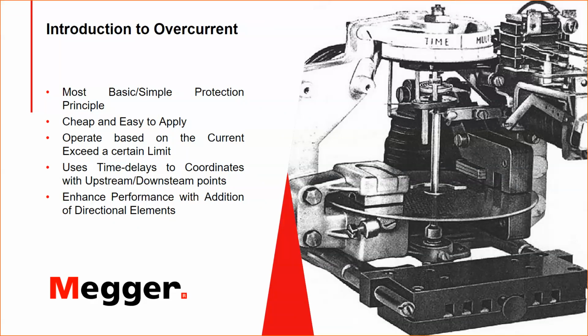Now, overcurrent can also be enhanced with the addition of directional elements. You can add a directional element to the overcurrent to see if the fault is in the forward direction or in the reverse direction. This gives you better selectivity and, in many cases, better speed as well. So directional overcurrent, since it's the most applied and what we are going to mainly talk about, we'll talk a little bit about it from a selectivity and time setting point of view.